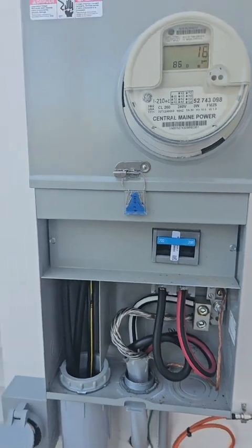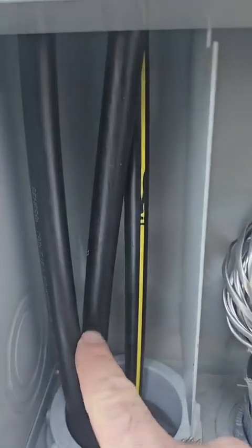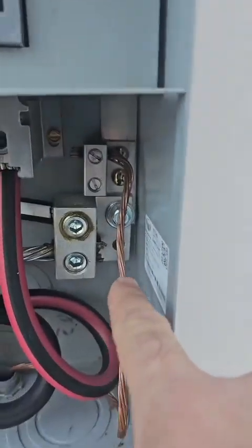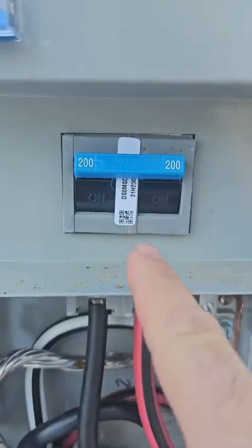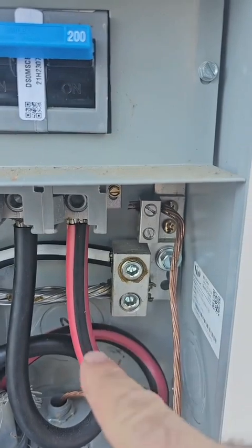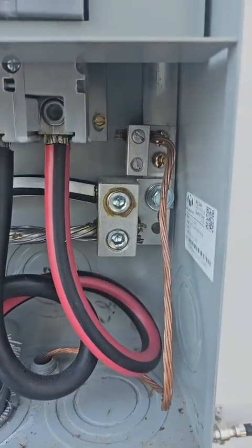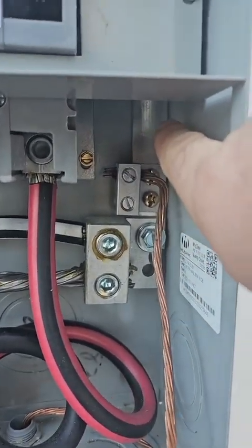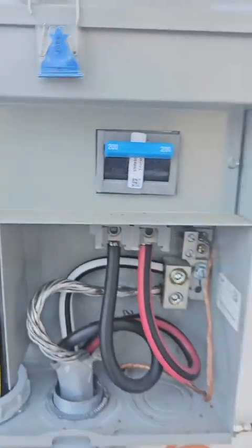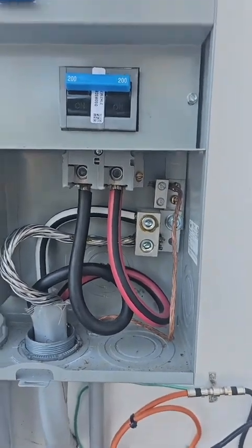All right, let's see some of those connections in real life. Here are two hots and a neutral. Goes up through the meter, down, and right here, right at the first breaker, first point of disconnect, all my neutrals and grounds come together. This strap right here is the neutral coming from above. All right, let's see what that looks like at the transformer end.